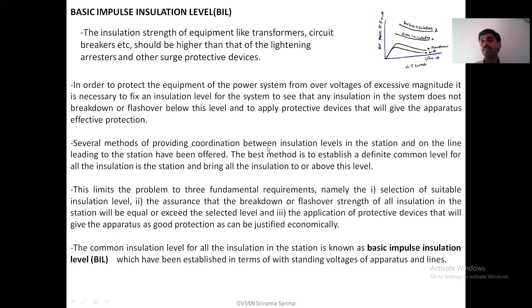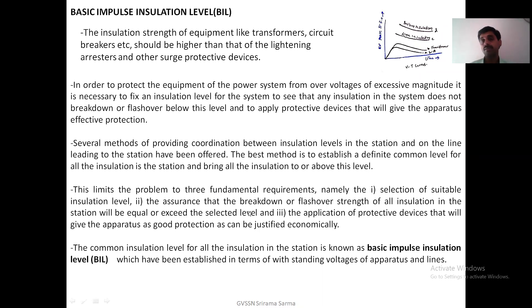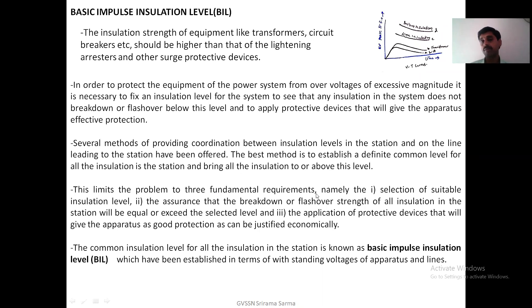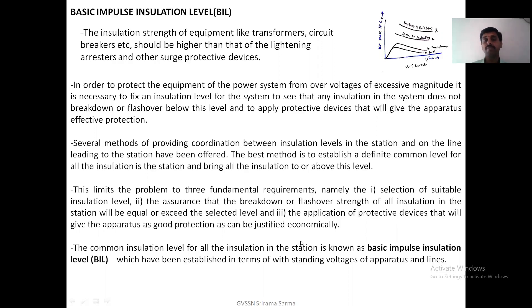Several methods for providing coordination between insulation levels in the station and the lines leading to the station have been offered. The best method is to establish a definite common level for all insulation in the station and bring all insulation to or above this level. BIL is the best method — establishing a common level so that every equipment insulation must be above it, and hence the entire equipment will be protected. Because of BIL, the problem is limited to three fundamental requirements: selection of suitable insulation level; assurance that the breakdown or flashover strength of all insulation in the station equals or exceeds the selected level; and proper application of protective devices for economical protection.